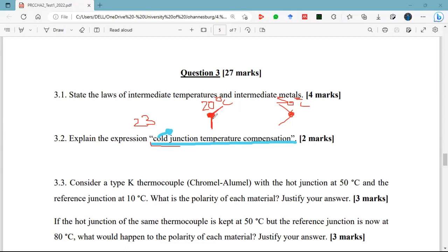And this is not something that you carry out manually this time in life. At this age, it's done automatically. So there might be a formula that is guiding that cold junction temperature compensation. But what they do actually, in words, because that is what you're looking for, that's why you're here, is just adjust the temperature measurements to account for the temperature difference that you could get between 2 points in your thermocouple circuit. Or even if it's not a thermocouple, because you don't only carry this out in a thermocouple. If you've got any follow-up questions on this, I'll take them now.